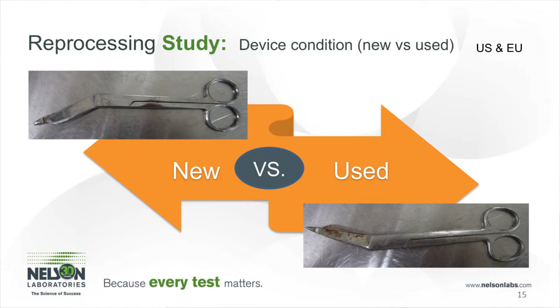The next thing to think about is the fact that the cleaning, sterilization, and disinfection validations will be the easiest to perform on brand new devices. So we want to make sure that the devices are in more of a used state going into validation. In this aspect, the FDA is requiring devices to go through some simulated use procedures to get the devices to be in a used state prior to the validation.